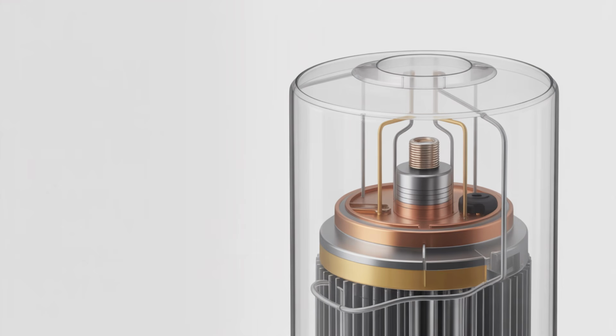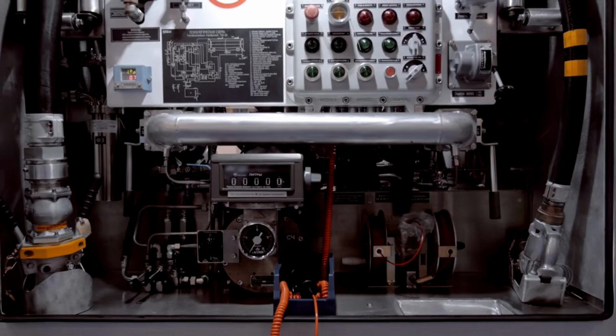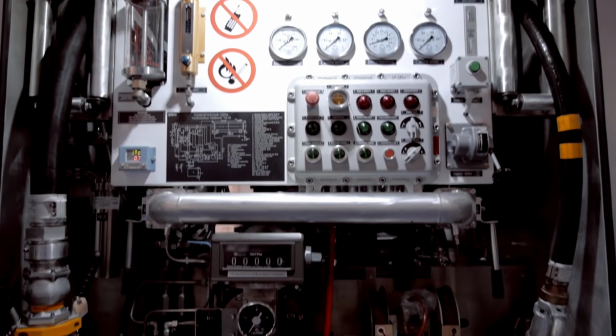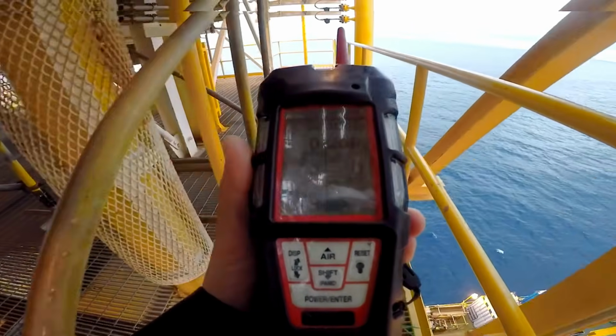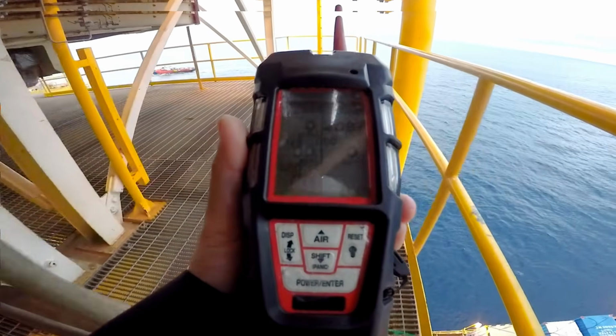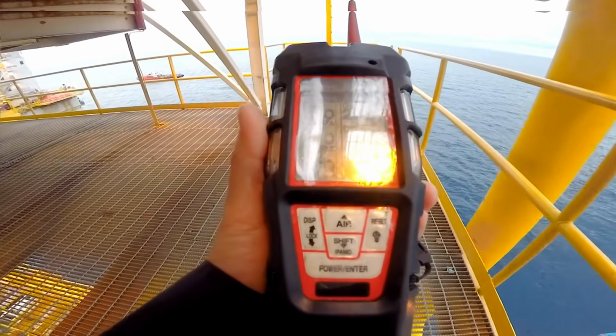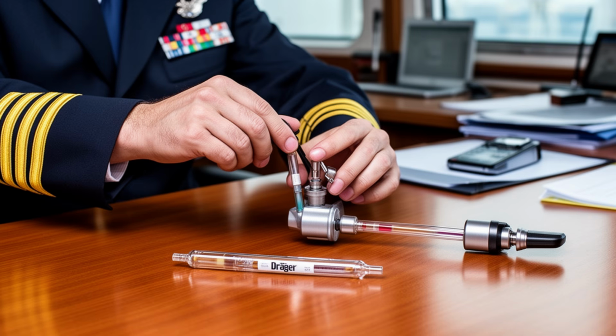Preparation for the officer interview is key. The surveyor will assess your familiarity with the equipment's purpose and limits. Can you explain when a sensor might be poisoned? For example, silicones or lead vapors can damage certain LFL sensors. You should know if your instrument can be used at above atmospheric pressure or in specialized environments. The surveyor will likely ask you to demonstrate a pre-operational accuracy test. Practice this until it is second nature. Show the self-test, zeroing in fresh air, and the actual response to the test gas as per the manufacturer's manual. If you use equipment from different manufacturers, be ready to prove they are compatible, such as tubes and hand pumps.